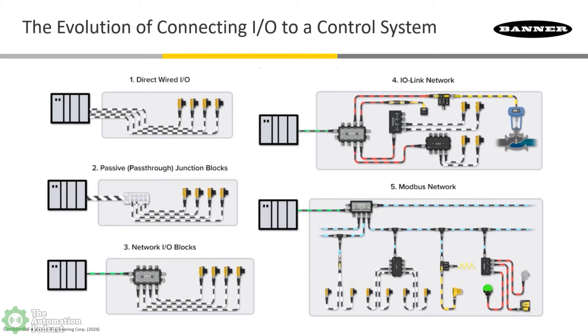Exactly. These are going to be IP67 and IP68. I totally agree with the trends we're seeing. Machine builders and manufacturers are moving to distributed and remote I/O solutions. In terms of PLC wiring, being able to simplify or reduce wiring also means significantly faster installation times for a lot of machine builders. Another thing is modularity — if you're a machine builder building a machine for an end user, and you have to ship it, the nice thing about connectorized connectivity is the quick disassembly and reassembly. If hardwired back to PLC input cards, you have to unscrew every screw terminal.